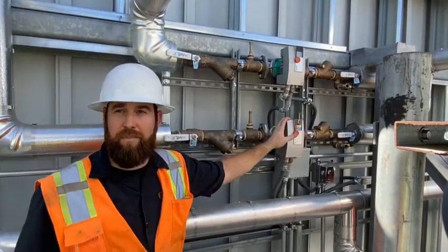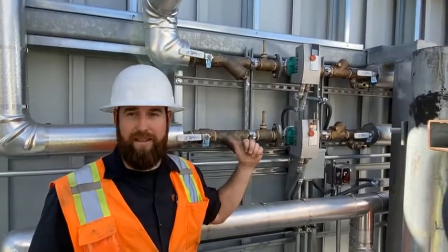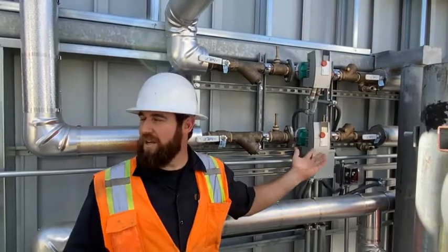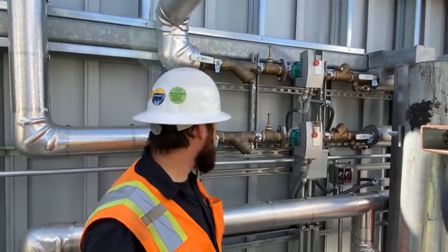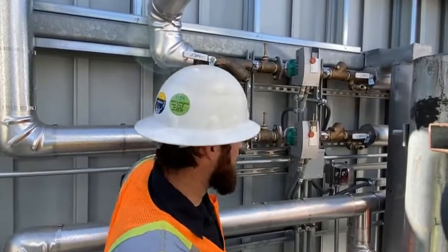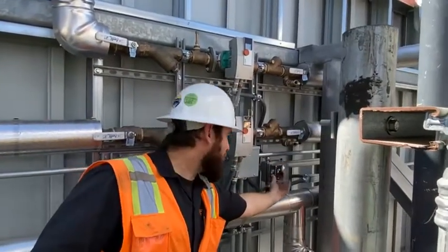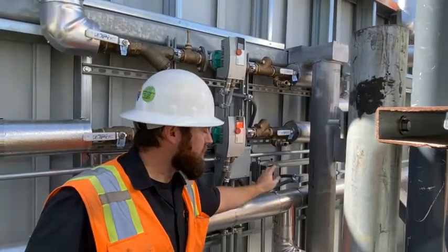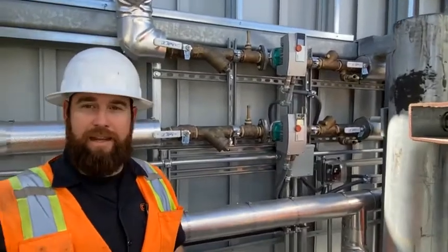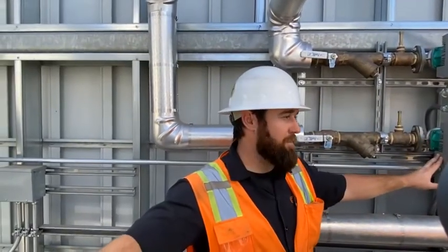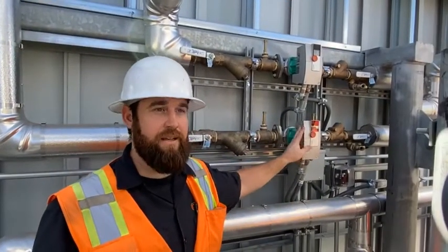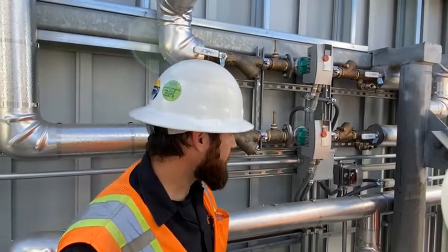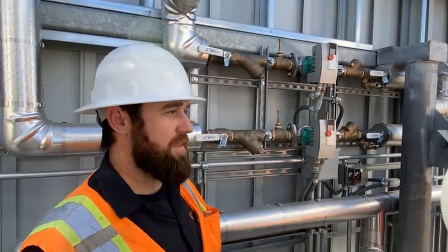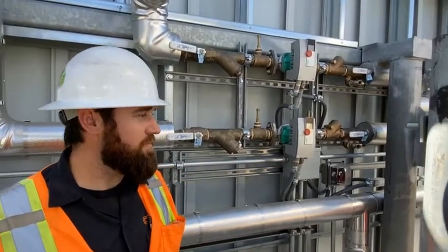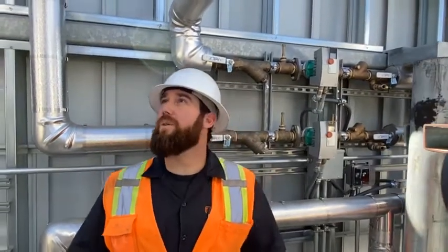The good thing about these pumps is they're maintenance-free. They're self-lubricated by the system fluids, so you don't really have to do a whole lot. Just check for leaks or anything like that. But yeah, again, we have isolation valves here and here. We got main power disconnects here, just switches. So when draining, make sure the corresponding pump is turned off first, and then isolate, and then drain. You don't want to isolate these pumps running because it can deadhead and damage the pumps. That's about that. Any questions so far? Pretty basic stuff. Pretty straightforward.